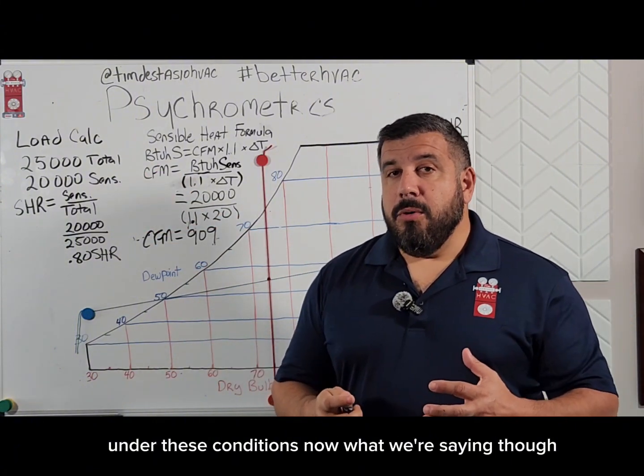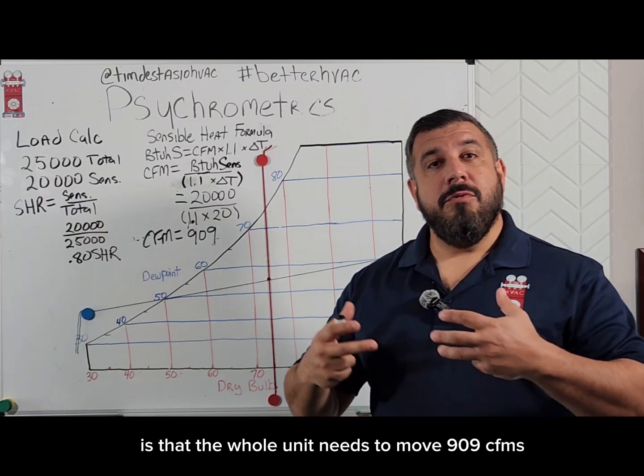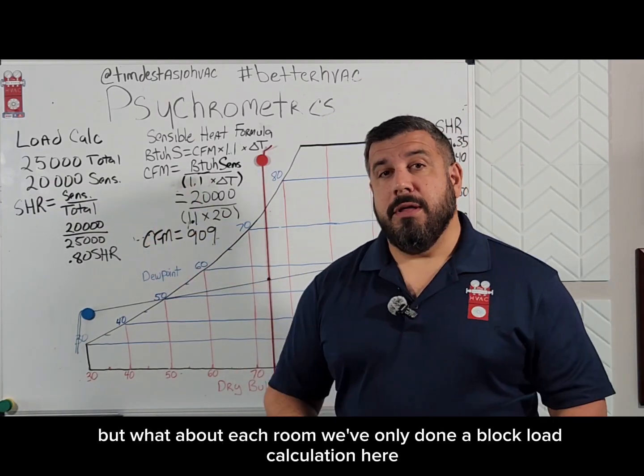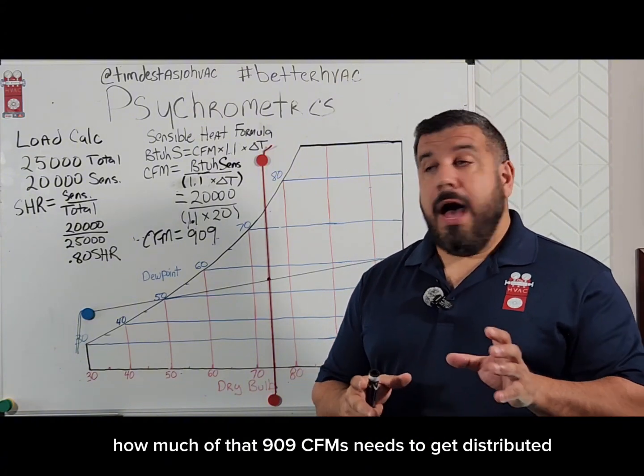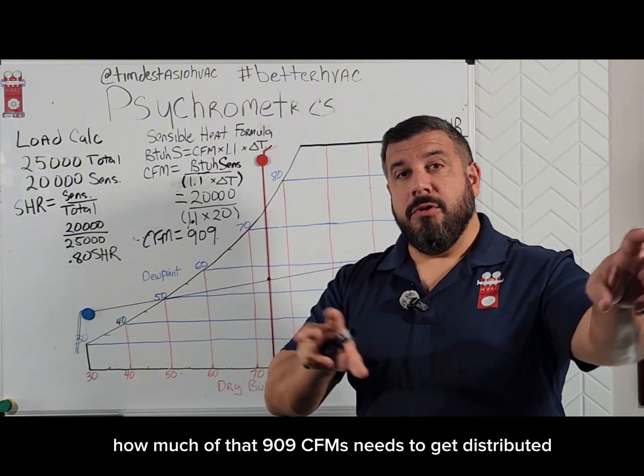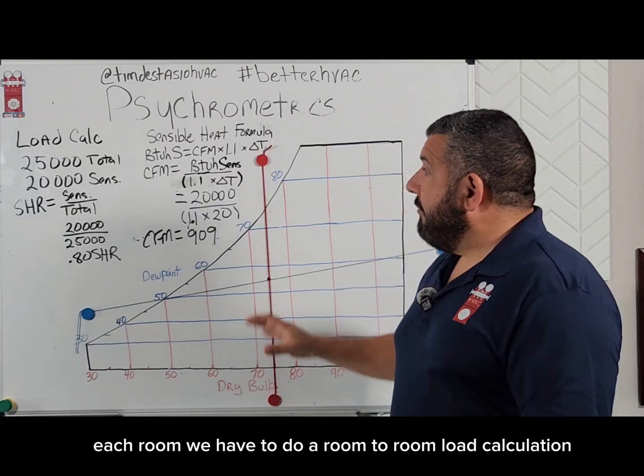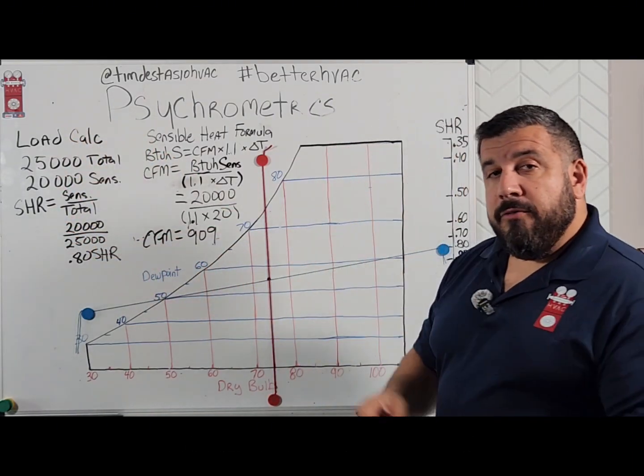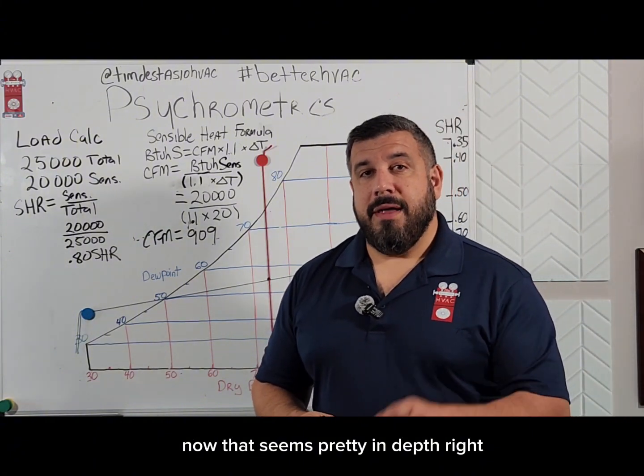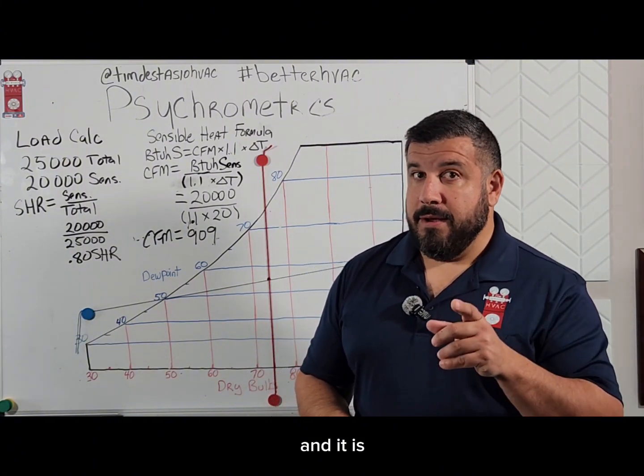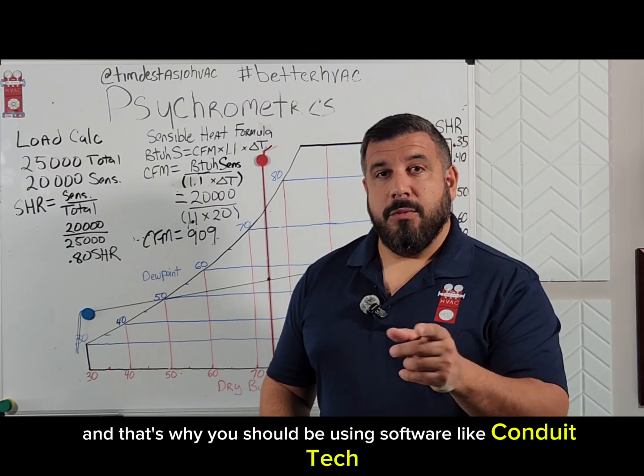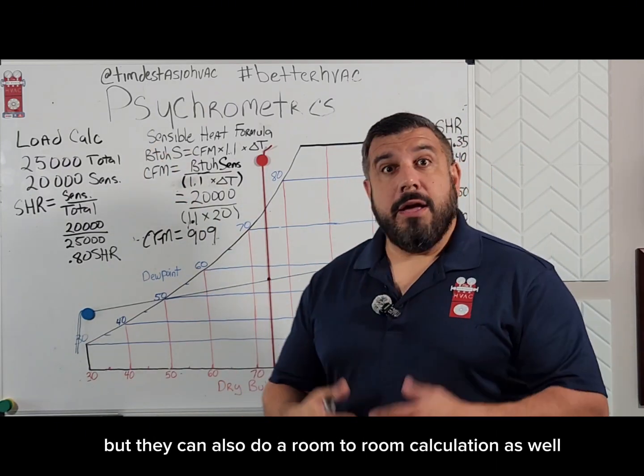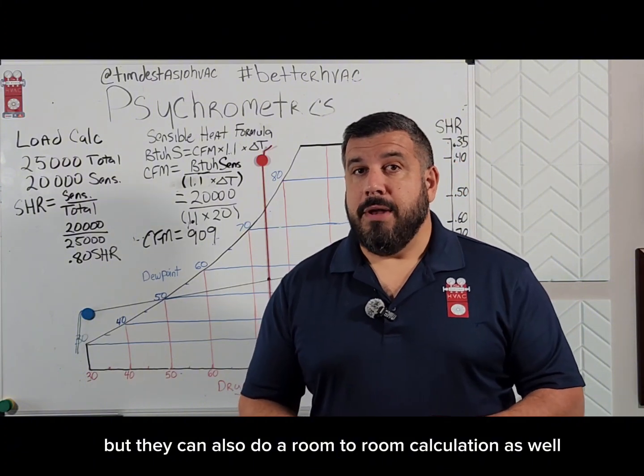The whole unit needs to move 909 CFMs, but what about each room? We've only done a block load calculation here. To determine how much of that 909 CFMs needs to be distributed to each room, we have to do a room-to-room load calculation, which means doing this whole process for every single room in the house. That's why you should be using software like Conduit Tech, which can do both block load and room-to-room calculations.